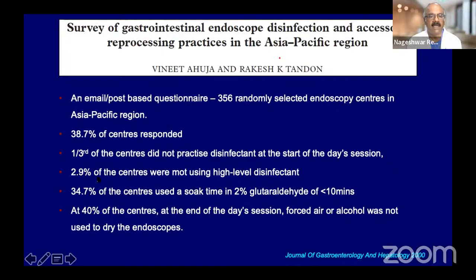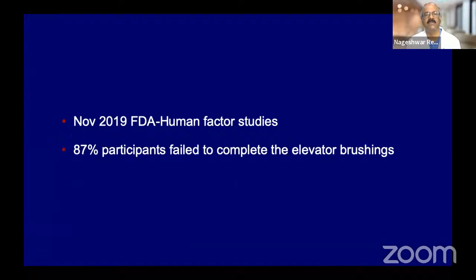But when you actually look at what is happening, you can see that 34% of the centers used a soak time of less than 10 minutes, which means that they were actually not properly sterilizing their instruments, and in 40% of the centers, forced air or alcohol was not used to dry the endoscope. In practice, when we do these surveys, we found that 50 to 60% of centers in the Asia-Pacific region, especially in the emerging countries, don't seem to follow the protocol of proper reprocessing of these endoscopes.